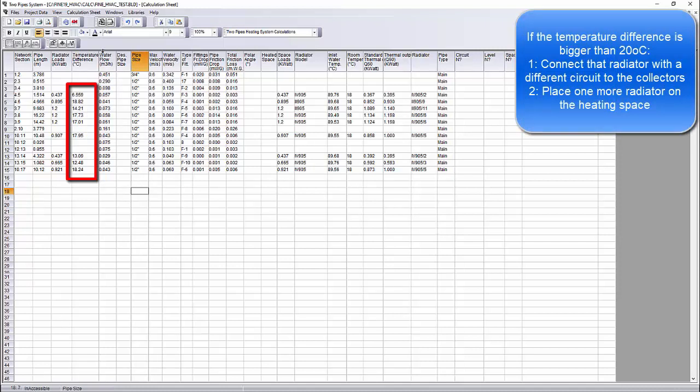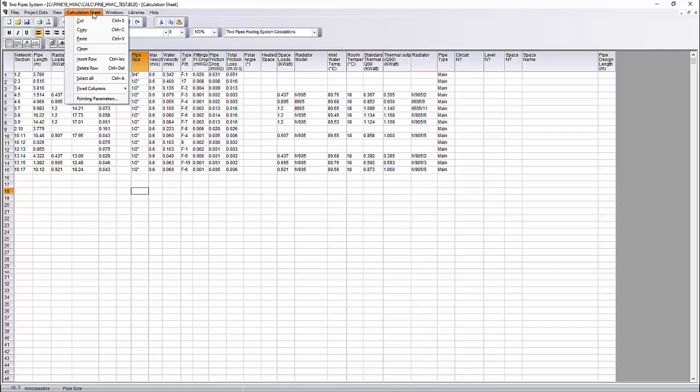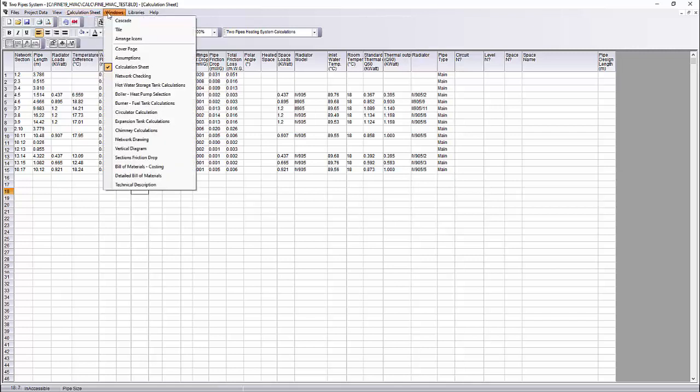We need to check if any radiator has temperature drop more than 20 degrees Celsius. If we had bigger temperature drop, we would need to change the network topology or to add one more radiator on that specified space. In that project, the temperature difference in every radiator is less than 20, so we do not need to make any changes.